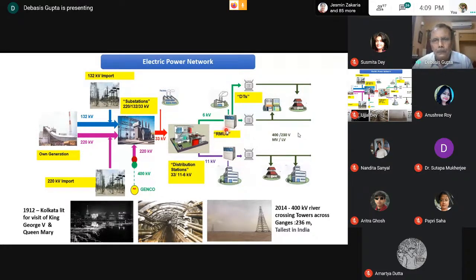After this, what has been put in by most utilities in India over the last 5-6 years is the RMU, ring main unit. These are very flexible 11 kV switchgear, SF6 filled switchgear. They can have either breakers or isolators, and they are placed at strategic locations throughout the city so that in case of a fault, you can isolate easily and see where the fault is. Then you can isolate the faulty section and restore from some other parallel ring main of that section.